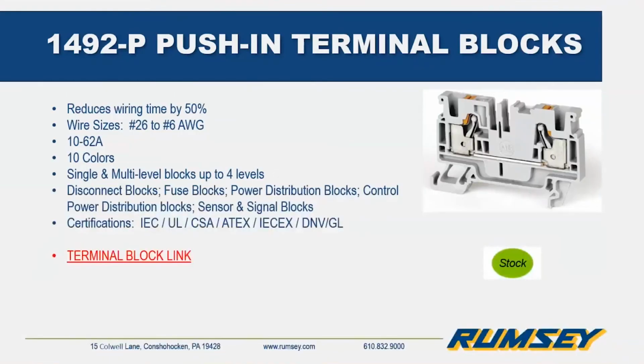So the push-in terminal blocks do reduce wiring time greatly. The wire sizes currently are 26 to 6 gauge, 10 to 62 amps in 10 colors, single and multi-level blocks up to 4 levels, and the various specialty blocks such as disconnects, fuse blocks, power and distribution and control, sensor and signal blocks. They're also ATEX rated, and we do stock them in Rumsey.